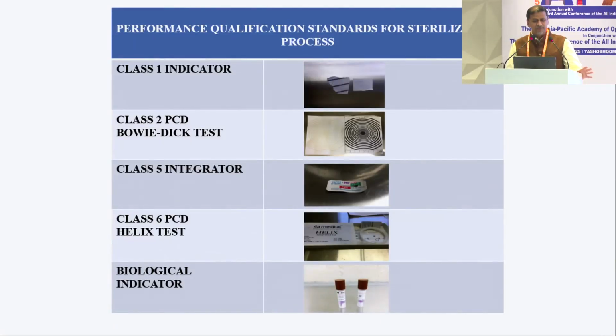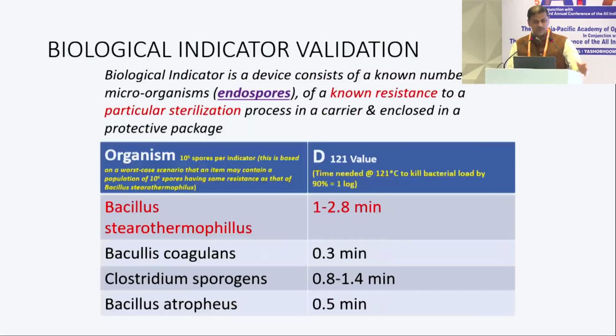So there are different types of autoclave indicators, and this comes among the performance indicator, which I'll be talking about later. The biological indicator, the spores to be used is Bacillus stearothermophilus, because this is the most resistant one. As I told you, 121 degrees Celsius is used because only at 121 degrees Celsius are the spores of Bacillus stearothermophilus completely destroyed. So this is the reason why 121 degrees Celsius and 15 minutes is used, because that is the time needed to kill the most heat resistant spores in your autoclave cycle.